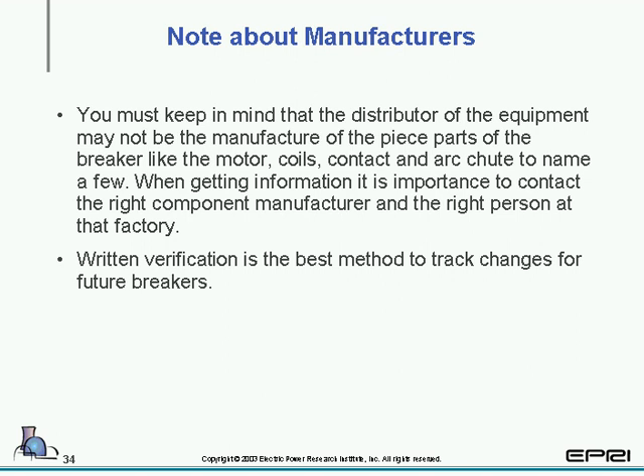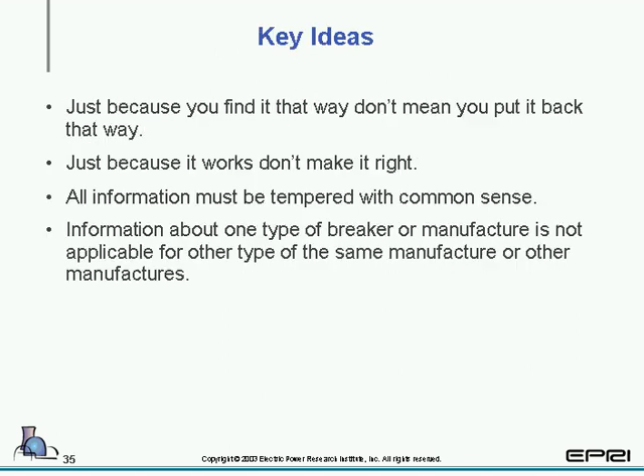And the last bullet. When you get some information from any manufacturer, the best way is written. Verbal is okay, but you'd be surprised what you get when you ask for it in writing. Key ideas: just because you find it that way doesn't mean you put it back that way. That's true of spacers, which are a huge challenge, and springs, and upgrades within the piece of equipment, breakers that have been implemented by the manufacturer.